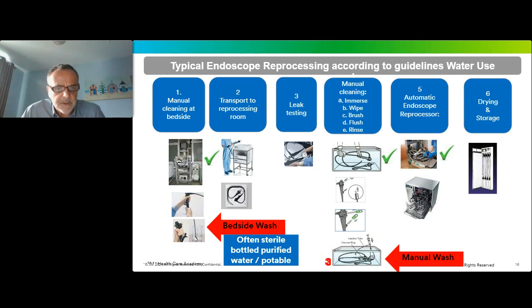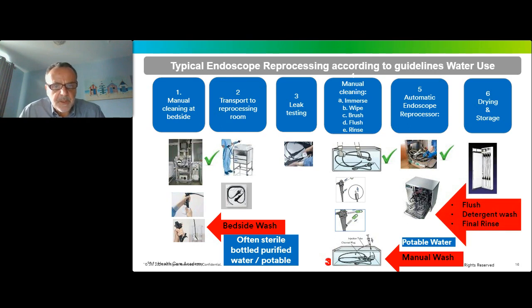Once the scope is transferred back to the reprocessing department, there would usually be a manual wash, and this often takes place in a sink or a basin with the addition of detergents, again to effectively remove any gross contamination. The scopes will then often be loaded into an automated endoscope reprocessing unit, which would generally speaking have a three-stage process: a flush to remove gross contamination, a detergent wash, and often then a chemical disinfectant wash, because obviously many endoscopes can't be thermally disinfected. They won't withstand the high temperatures required.